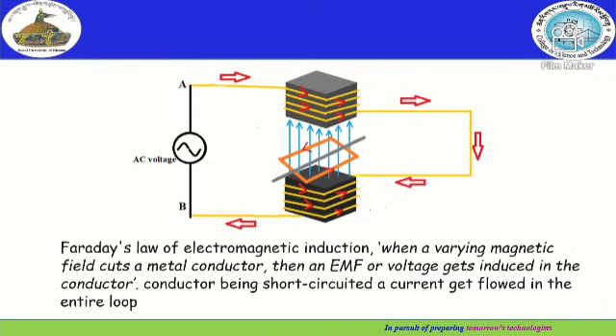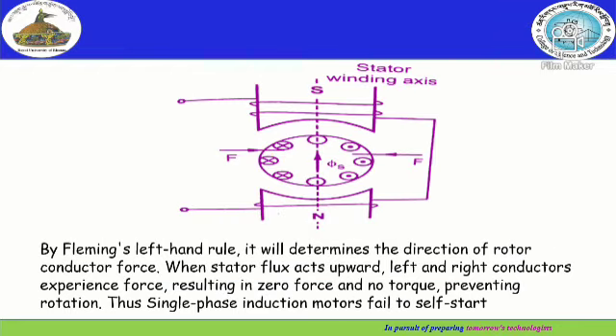Since the rotor is short-circuited, current will flow through the entire loop of the conductor. Using Fleming's left-hand rule, we can determine the force experienced by each conductor. The conductor on the left side will experience a force from left to right, and the conductor on the right side will experience a force from right to left, resulting in zero net force and no torque. With no torque, there is no rotation — that is why the single-phase induction motor is not self-starting.